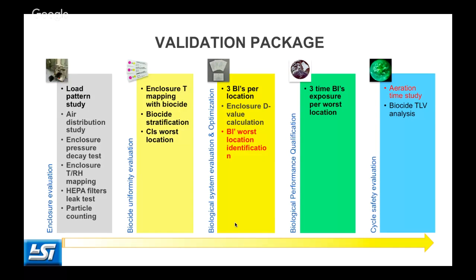In an evaluation of the enclosure with the load pattern study. So we need, for instance, I cannot sit a container on a hard surface, because below on the lower part of the container, the hydrogen peroxide cannot enter, cannot penetrate. So I could have issues in making the decontamination of this part. All the shelves are wired shelves in order to minimize the contact with the products that are supported, and to guarantee the better distribution of the hydrogen peroxide.